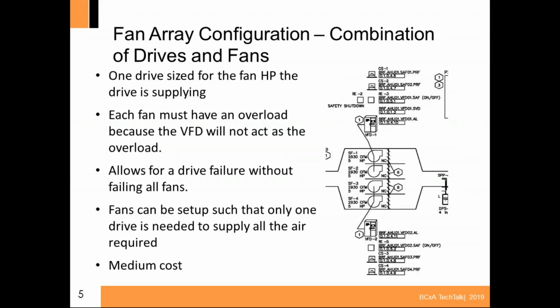The other setup is kind of a combination of the two. This is a 4-fan wall in which you have 2 fans on one drive and 2 fans on another drive. This is an application where they wanted to have redundant fans, and we convinced them that we could use this setup to show as redundant. We had to calculate how each drive worked with every 2 sets of fans, such that if one drive failed, the other 2 fans could make up the difference enough to keep the space safe. Or if one fan failed, we could also ramp up the other fan to maintain the differential set point or flow rates that we're looking for.